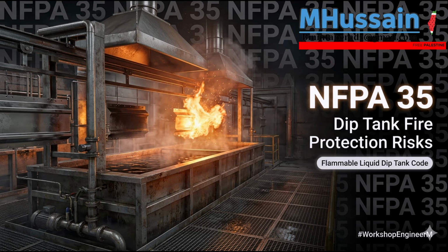Okay, Div 1. That means ignitable concentrations of vapors are expected to exist under normal, everyday operating conditions. Just as a matter of routine. Right. So everything within that zone, typically a 5-foot bubble around the equipment, must be heavily armored, explosion-proof electrical gear. Switches must be sealed so any internal electrical arc is contained and cannot ignite the outside air.